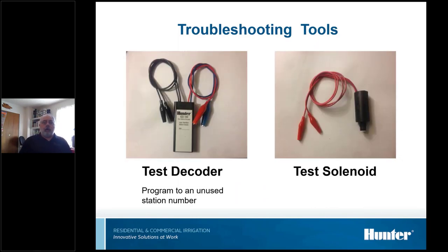This is a picture of my test decoder and my test solenoid. I just programmed the decoder to station 99. If I'm working on an ACC, I'll turn it to station 75. If I'm on an ACC2, or I'll turn it to 48 if I'm on a dual system, just depending on what system was what station number I set into it. And then I can just substitute it in and try to turn it on anytime I want. And the solenoid, you just hook it up and see what happens.